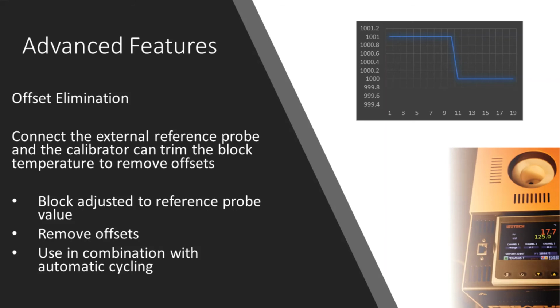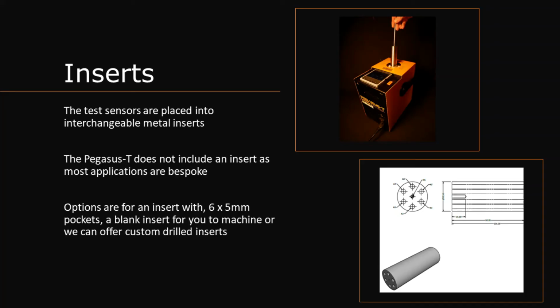Offset elimination. Connect an external reference probe and the calibrator can adjust the block to the reference probe value to remove any offsets. This can be used in combination with automatic temperature cycling. Test sensors are placed into interchangeable metal inserts inside the furnace. The Pegasus T does not include an insert as most applications are bespoke.